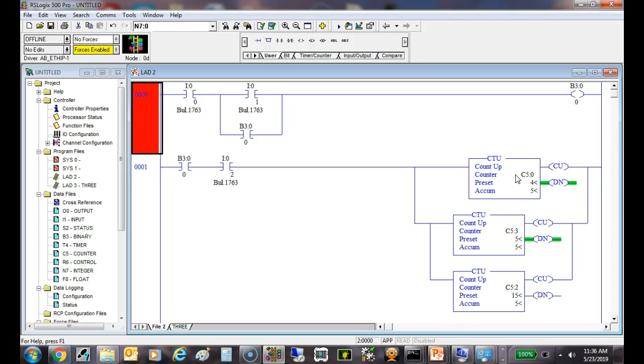Everybody okay on counters? So what do counters need? All right, Siemens still uses blocks for counters. But what were the types of counters that y'all remember from back when we could run into in PLC, not just Allen Bradley? Cascading is just taking one and feeding it into another. We could have a single input counter, or we could have a double input counter. So on the Allen Bradleys, it becomes enabled when you bring this input right here to it. Siemens uses these two input counters. Siemens has up-down counters, but all of them are enabled. We'll have to build around that, right? Understand that.